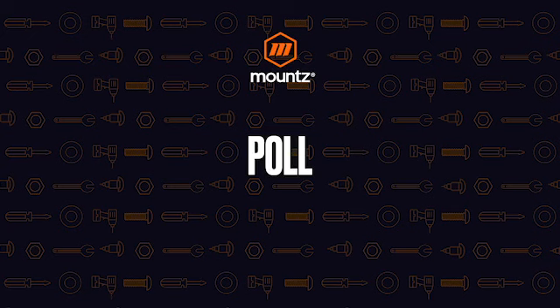All right. Thank you very much for participating in that. It looks like about 75% or so use outside vendor services for their calibration, and about 25% or so do it in-house. So what is involved in the calibration process? One of those items is going to be the calibration interval. At what point do you recalibrate a torque sensor in that setting?